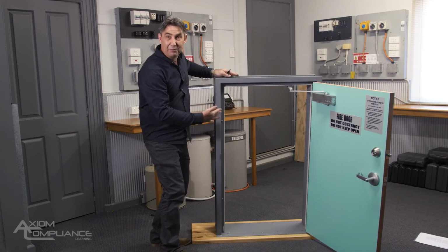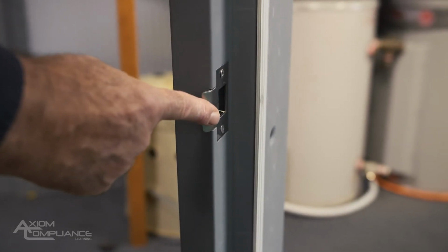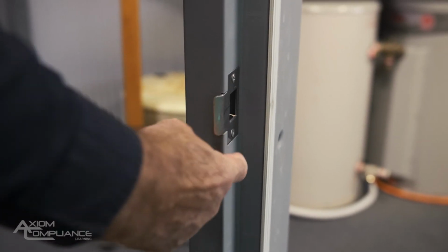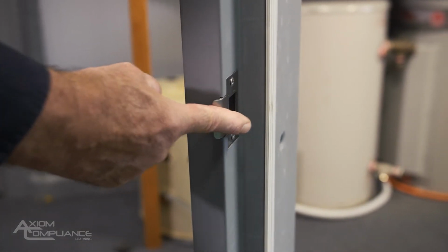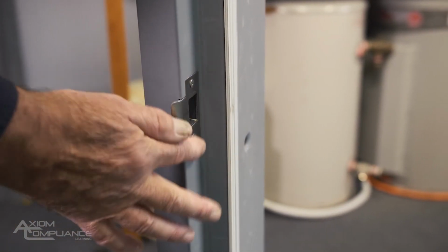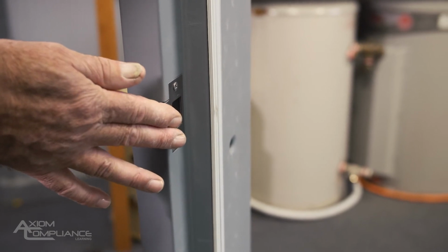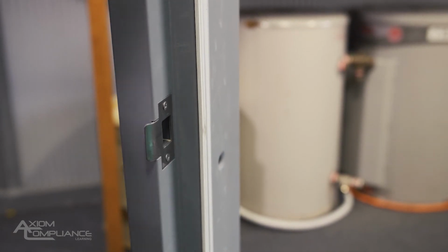while I'm here and while we've got the door open, we should be looking at the striker plate. The door striker forms a really important part of the door closing action, so it must be recessed into the door frame, and it's got to have this beveled edge on it to aid the closing of the door. So if you don't have a door striker plate, it's an immediate fail on the door and you've got to replace that striker plate. It must be the same striker plate as the door lock set as well.